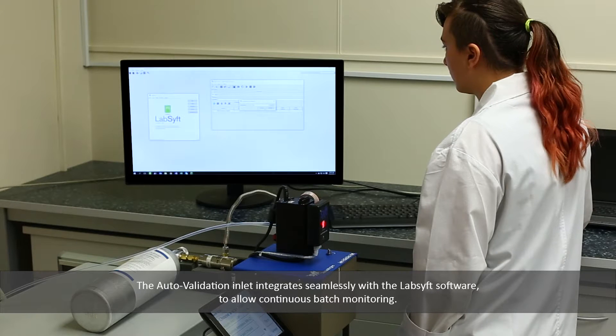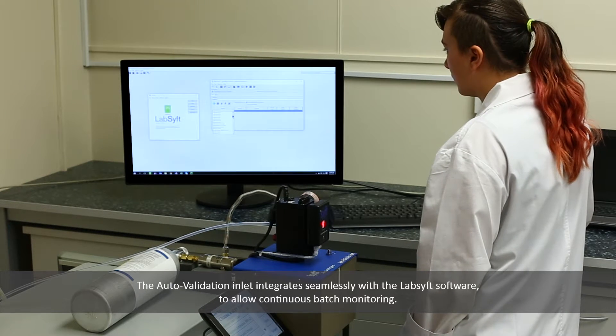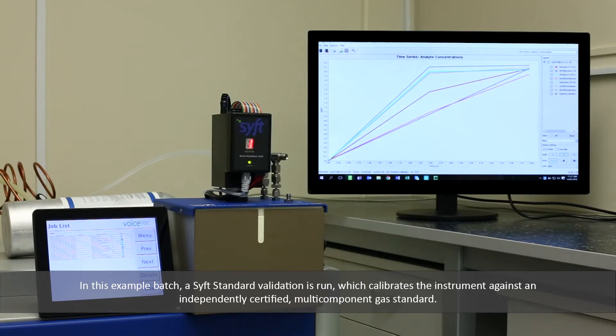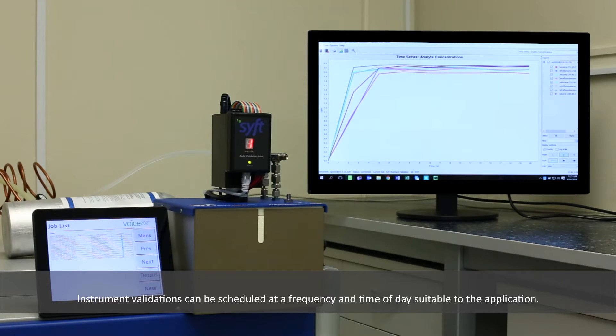The auto-validation inlet integrates seamlessly with the LabSyft software to allow continuous batch monitoring. In this example, a Syft Standard validation is run, which calibrates the instrument against an independently certified multi-component gas standard. Instrument validations can be scheduled at a frequency and time of day suitable to the application.